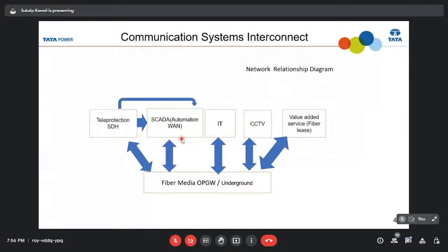Next is SCADA, supervisory control and data acquisition system. To simplify, this is automation, remotely operating a substation from a centralized location. Suppose my substation is located at Bhandup, and I want to open a breaker there, the command is given from Trombay. This command is transmitted through our fiber optic network to Bhandup, and from there the breaker is opened. This is possible only through an automation network connected to the servers at Trombay, and only through fiber optic media.